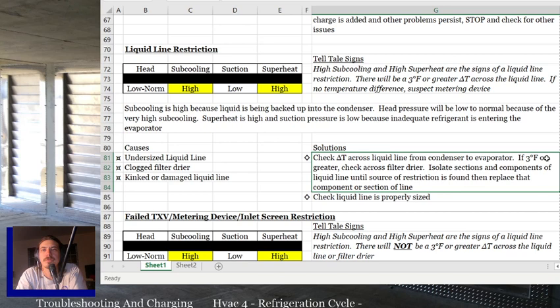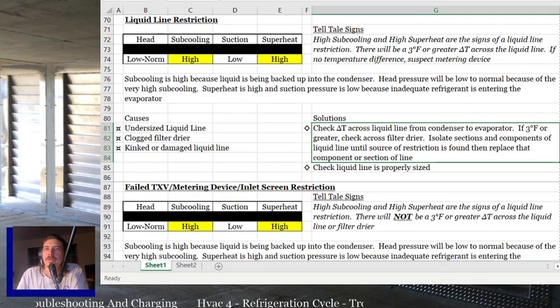If the issue is the filter dryer, obviously replace the filter dryer. That's your most common issue, is a clogged filter dryer. If you got a liquid line restriction, and like I said, the next one would be you just got a kink in the liquid line and you got to cut that piece out and put a new piece in.